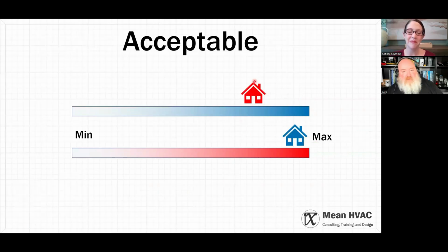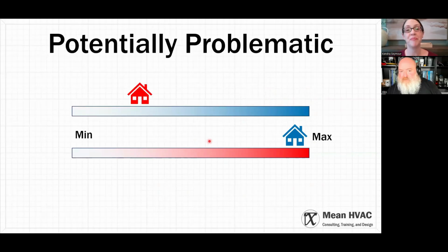So if you're somewhere in here where the thing is kind of oversized, that's not great, but if you're within 30% of that max, you'll be okay. This is what we run into up north a lot, and it's very likely to have dehumidification issues.